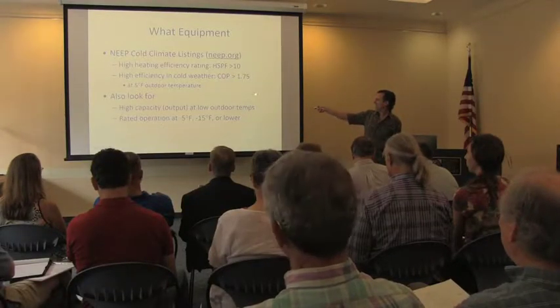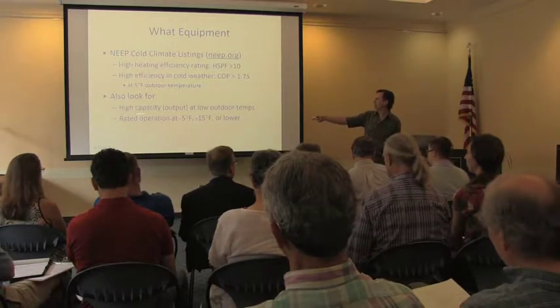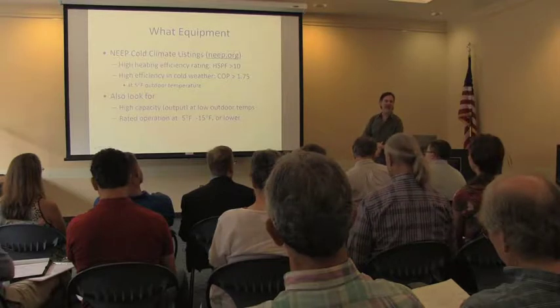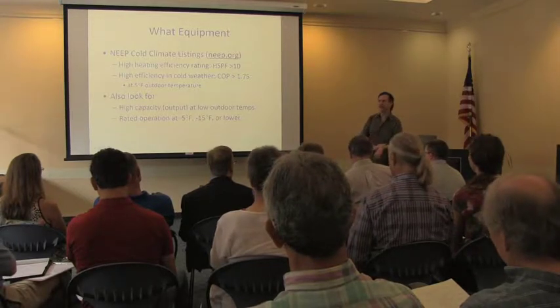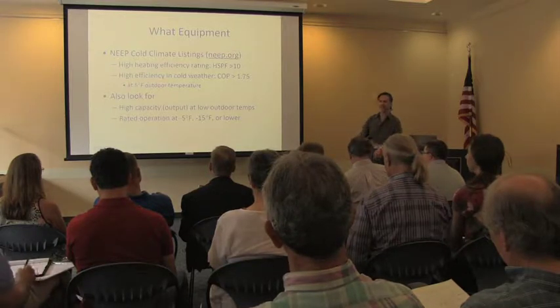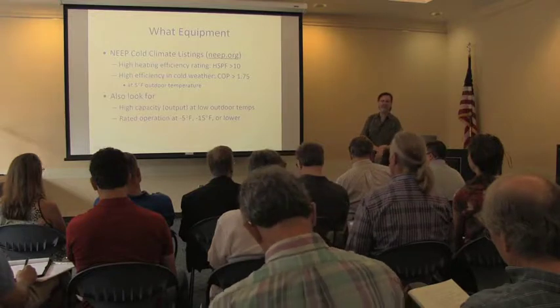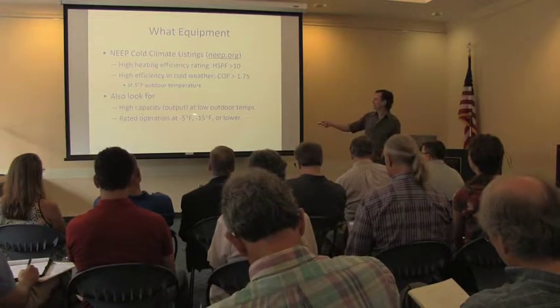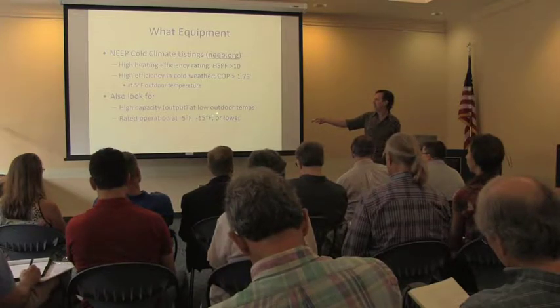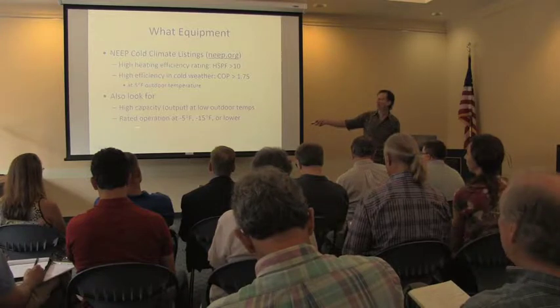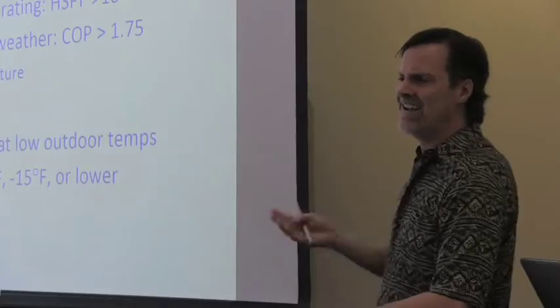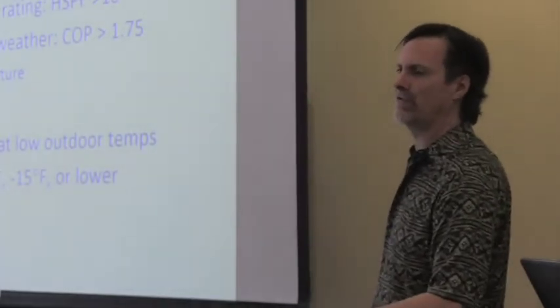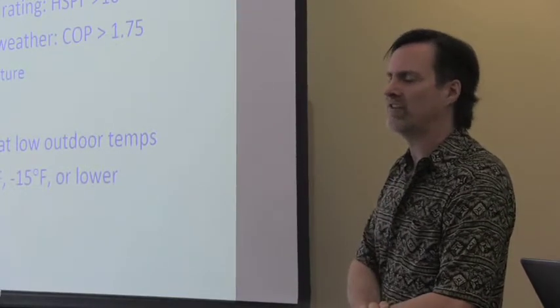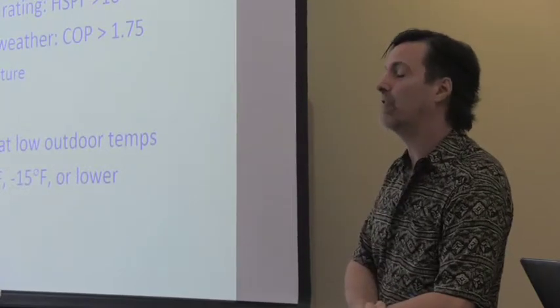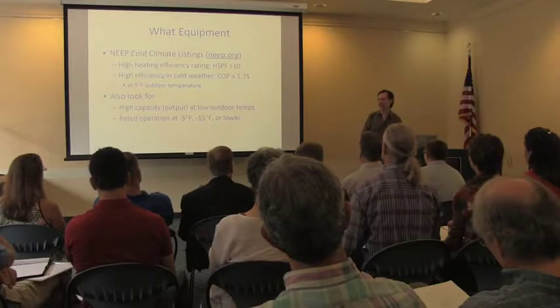Other things to look at, and these are not requirements for the NEEP cold climate listings, but look for equipment that maintains a high output at cold temperatures. You can get that from looking at these listings because they're required to disclose their performance at 5 degrees, at 17 degrees, and at 47, so you can see which ones maintain high outputs at very cold temperatures. And many of these systems have rated operation down to minus 5 or minus 15. Like I said, that doesn't mean they shut off at minus 5 or minus 15. They'll still keep working and producing heat. In my case, I've had nights that are down to minus 25, minus 27, and my heat pump's still producing heat. I've never had to use supplemental heat in my house. And I still don't turn on the upstairs unit in the winter.